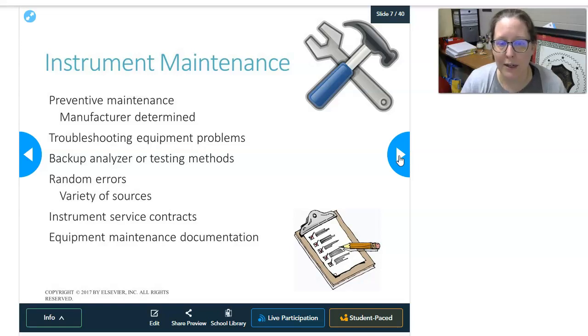Also, random errors occur on analyzers. It can have a variety of sources. Some of that can be linked to instrument maintenance if cleaning is not done appropriately, and it's because maybe probes are dirty, or some area is dirty, and that's causing some random errors.